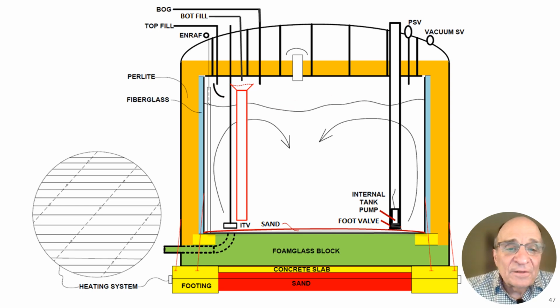Newer tanks are configured without this bottom penetration. Most of them are. You can still buy it with a bottom penetration if you so desire, but most of the newer tanks consist of these tubes that are coming down with the internal tank pumps. But then how do you bottom fill if you don't have a bottom penetration? You bottom fill by way of having a pipe that comes down to the bottom. Your LNG comes in here, comes into this funnel type of configuration, and the LNG is delivered to the bottom of the tank.